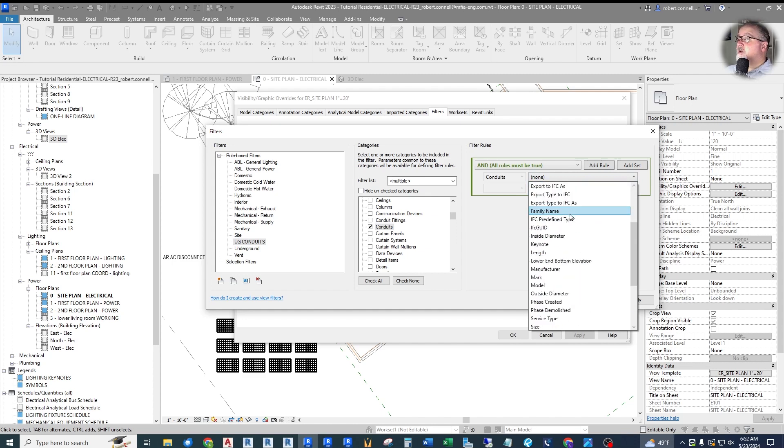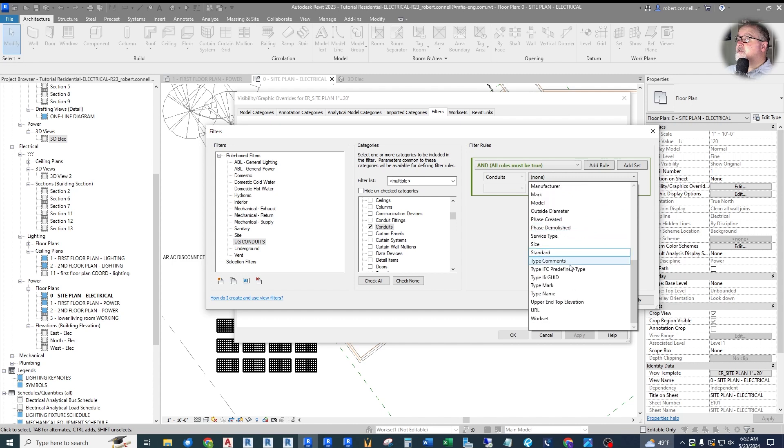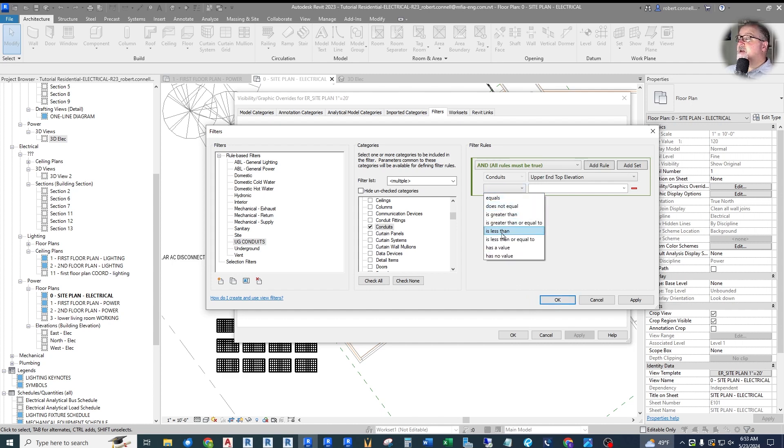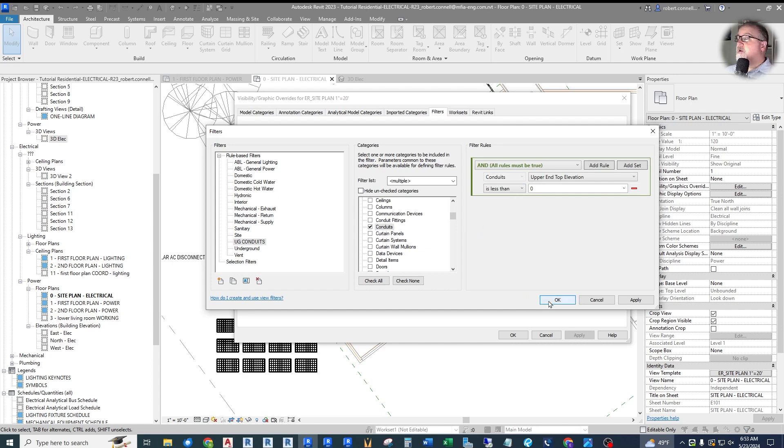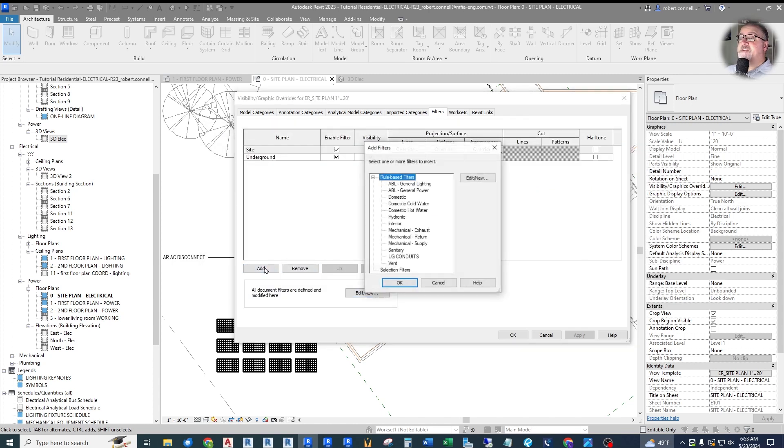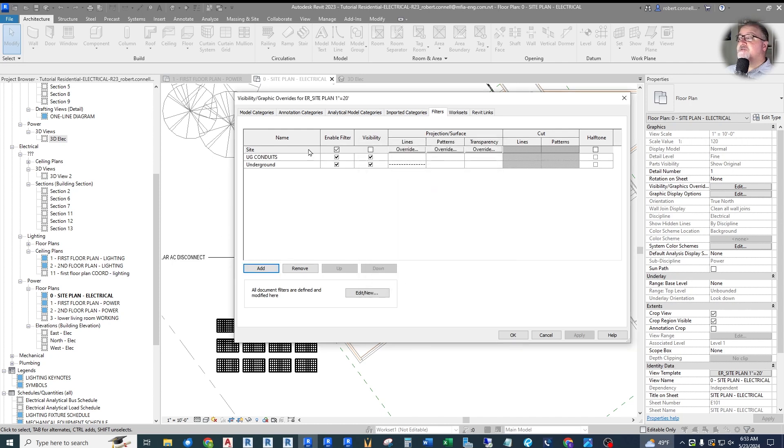I can go to conduits. I can look at where they are. We have length, diameters, things like that. Here's upper end top elevation. So I can check the top elevation of my conduit. And I can say is less than 0 below my level. So conduits where the upper top elevation of the conduit is less than 0, below ground, below grade. Then I need to add this filter to this view.